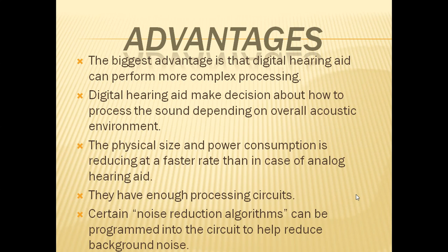Some of its advantages are: the biggest advantage is that digital hearing aids can perform more complex processing. They make decisions about how to process the sound depending on the overall acoustic environment. The physical size and power consumption are reducing at a faster rate than in the case of analog hearing aids. They have enough processing circuits. Certain noise reduction algorithms can be programmed into the circuit to help reduce background noise.